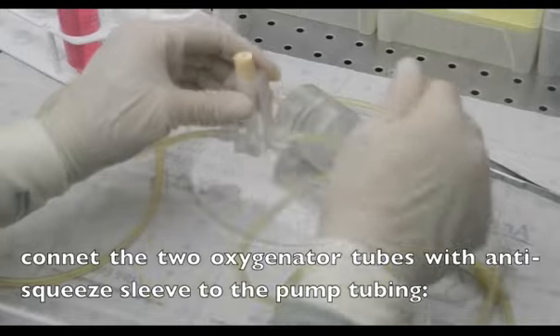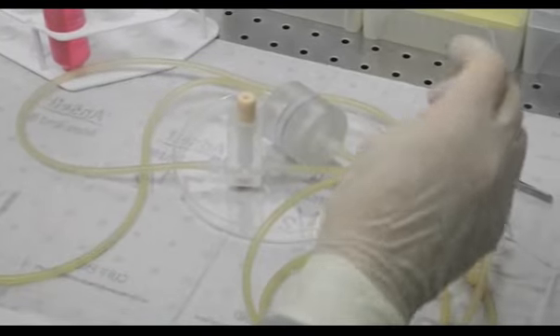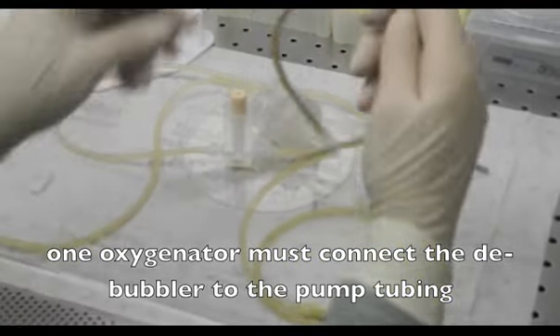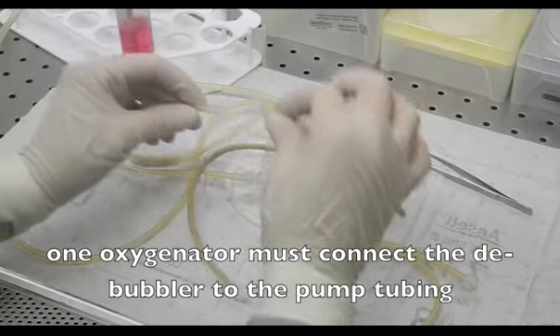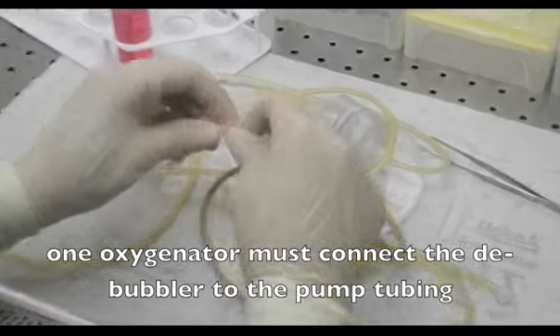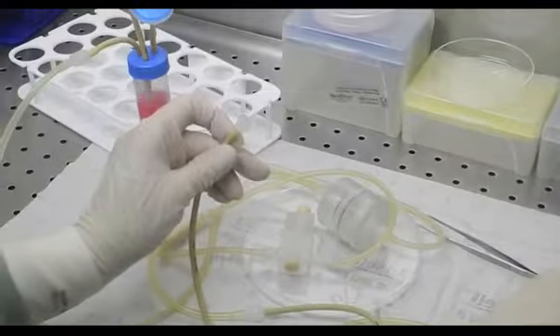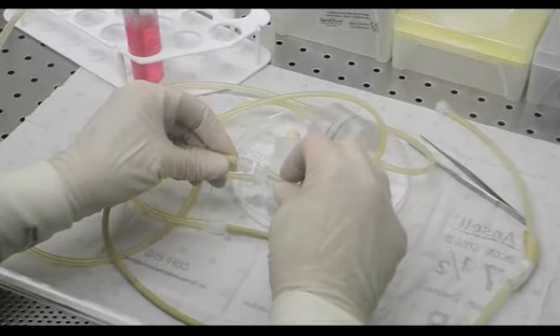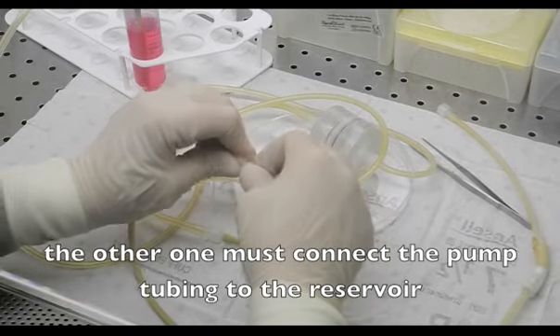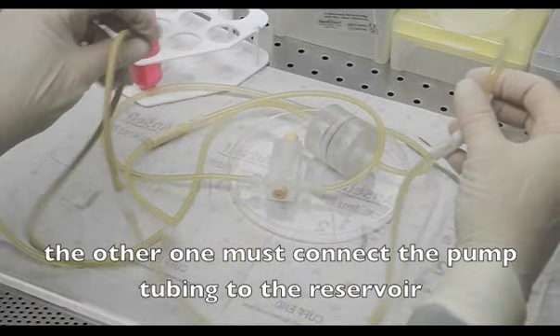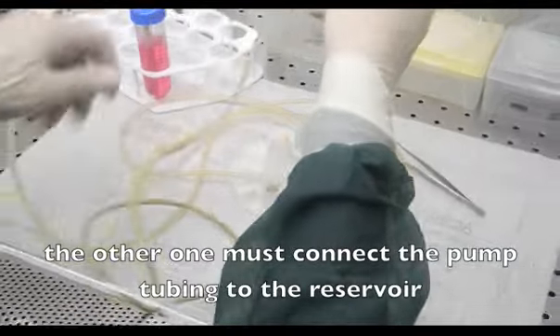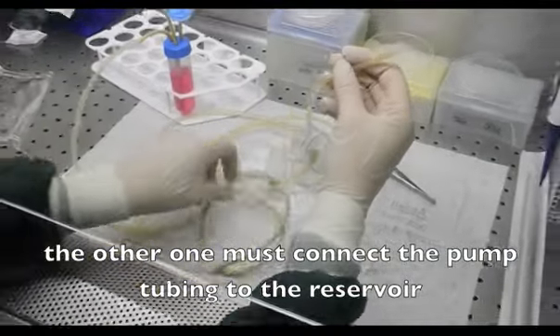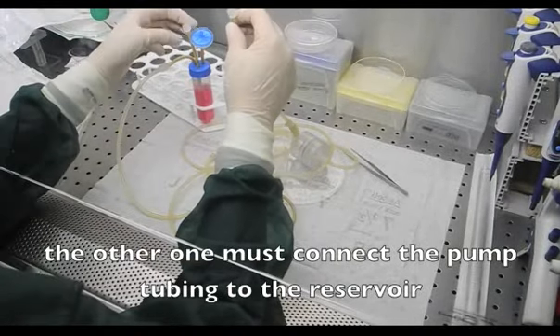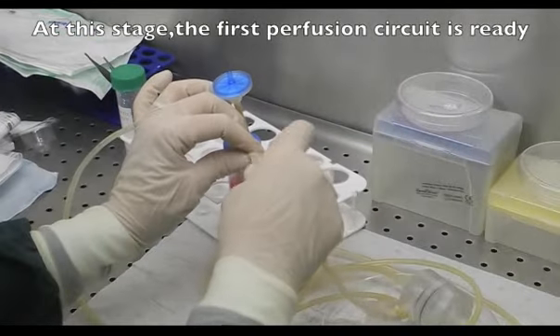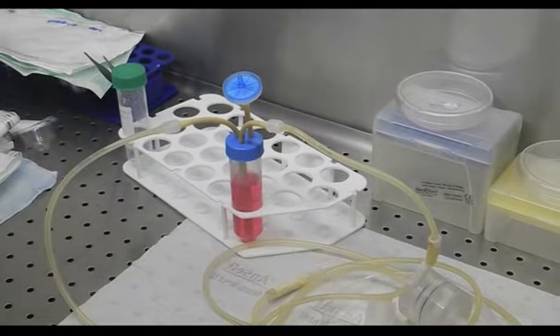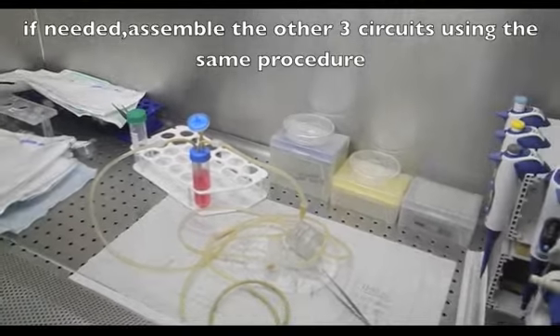Connect the two oxygenator tubes with anti-squeeze sleeve to the pump tubing. One oxygenator must connect the debubbler to the pump tubing. The other one must connect the pump tubing to the reservoir. At this stage, the first perfusion circuit is ready. If needed, assemble the other 3 circuits using the same procedure.